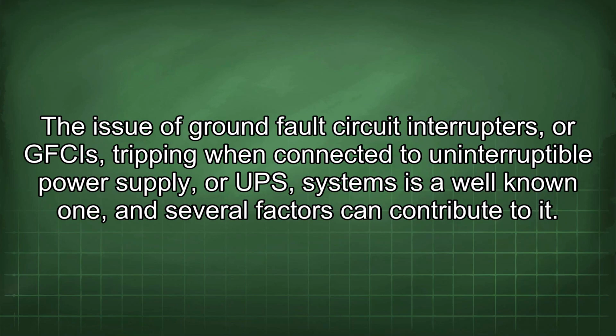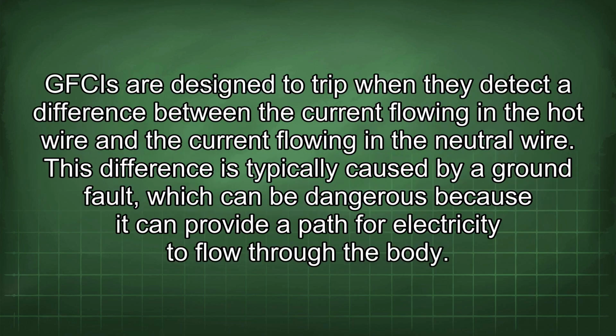The issue of ground fault circuit interrupters, or GFCIs, tripping when connected to uninterruptible power supply, or UPS systems is a well-known one, and several factors can contribute to it. GFCIs are designed to trip when they detect a difference between the current flowing in the hot wire and the current flowing in the neutral wire. This difference is typically caused by a ground fault, which can be dangerous because it can provide a path for electricity to flow through the body.